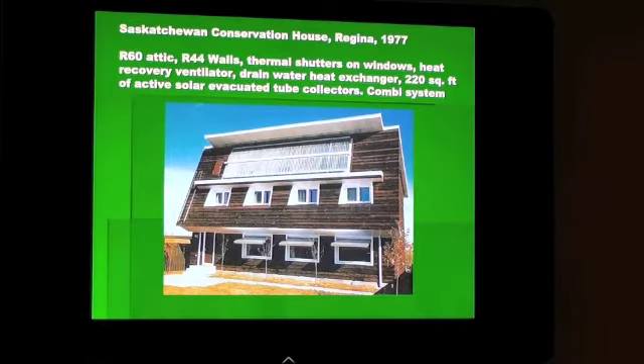This building is doing that as well with the south-facing window. One advance on the house is that they've incorporated thermal mass on the floor — one and a quarter inch thick concrete tiles that absorb heat during the day and release it at night. It allows the building not to overheat during the day, and in the summer time this will work as well to prevent the building getting too warm.